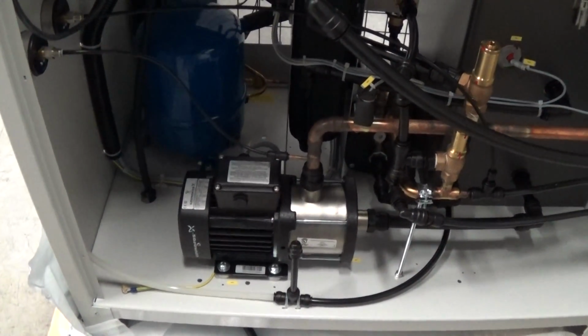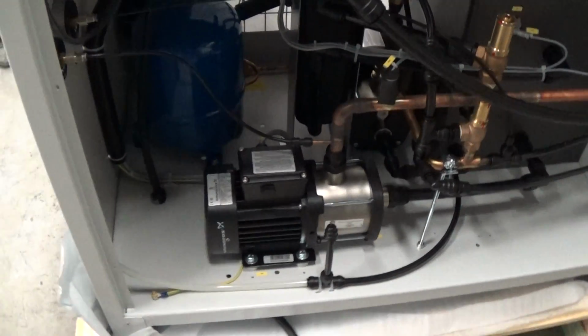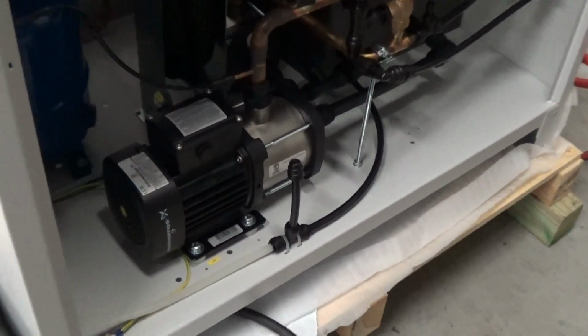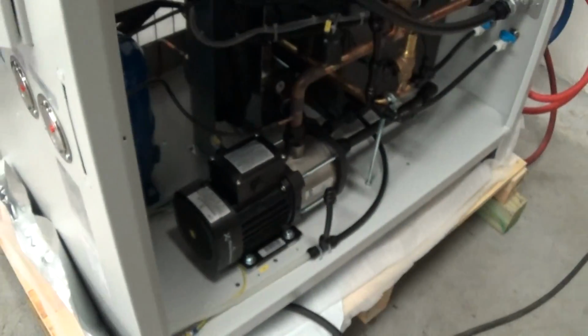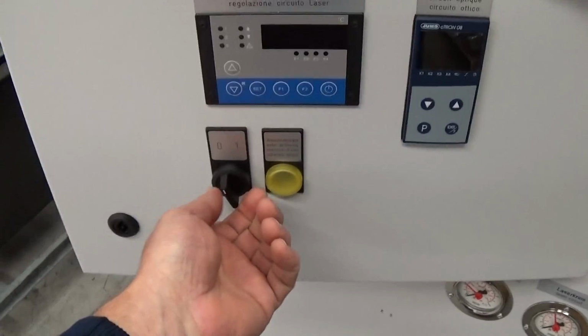These are phase dependent as far as rotation goes. The Grundfos pumps are a little bit different than what some people might be accustomed to. Their rotation, when you look from the rear, you can see that. Their rotation is actually counterclockwise as opposed to clockwise. So when you first put power to this unit, and you're probably going to want to snake power up through here and then up into the control enclosure, when you first put power to the unit, get a helper here with a flashlight, and you're simply just going to toggle this quickly, the power on.